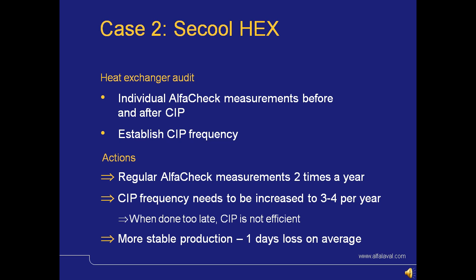We also discovered that the CIP frequency needs to be increased to 3 to 4 times per year. As I mentioned before, if the heat exchanger is badly fouled or even has clogged channels, then the chemicals cannot enter those channels or do not have sufficient time to work in the heat exchangers, meaning that the plate will not get cleaned. The channel will not get cleaned, some sections of the plate might not get cleaned well enough. But if you do CIP in time, where the fouling is not too severe, then the chemicals can work efficiently, and this is a very time efficient and cost efficient process for cleaning the heat exchangers.